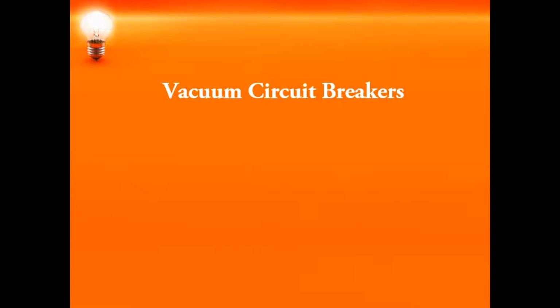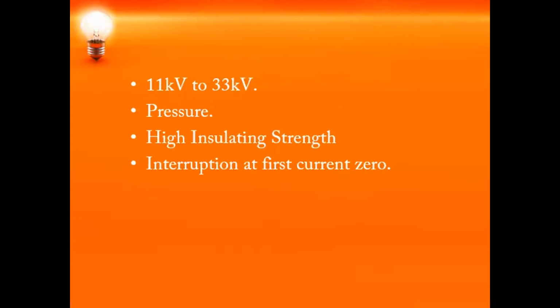Welcome you all to the session on vacuum circuit breakers. So what is meant by vacuum circuit breaker? We have seen the air blast circuit breaker and the air break circuit breaker, where air is used as an arc quenching medium. Similarly, if we use vacuum for quenching the arc, then we call it a vacuum circuit breaker.